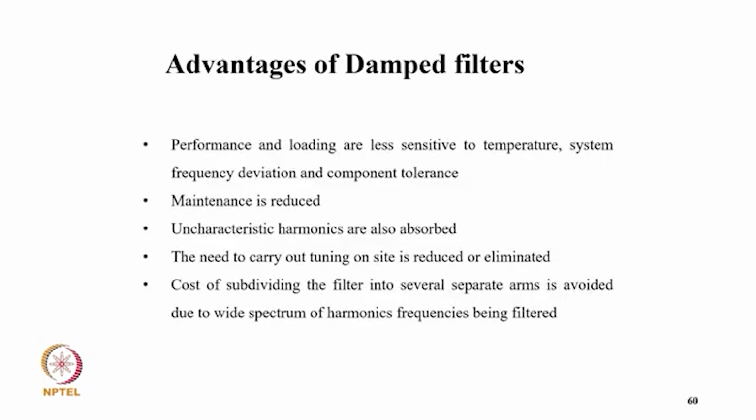Coming to the advantages of the damped filter, the performance and loading are less sensitive to temperature, system frequency deviation, and component tolerance, maintenance is reduced, and uncharacteristic harmonics are also absorbed. The need to carry out tuning on site is reduced or eliminated. The cost of subdividing the filter into several separate arms is avoided due to the wide spectrum of harmonic frequencies being filtered.